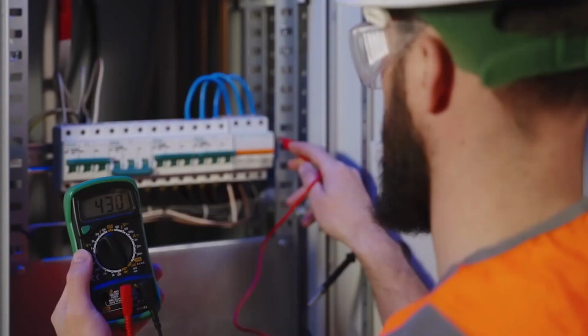Construction groups are typically responsible for certain pre-commissioning activities, but when construction groups don't understand their role to contribute to successful commissioning and startup of the facilities, this lack of understanding can lead to incomplete pre-commissioning tasks that cause bigger problems later. For example, poorly done flushing can leave debris inside mechanical piping, and lumber that remains within pipes will restrict flows during later performance testing.